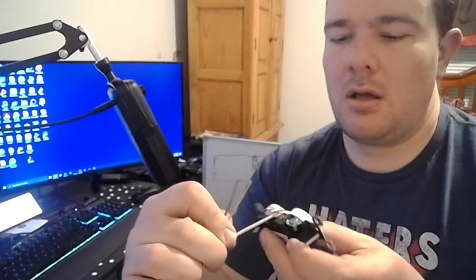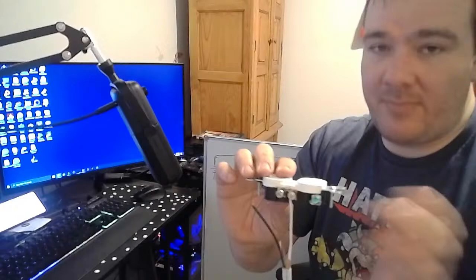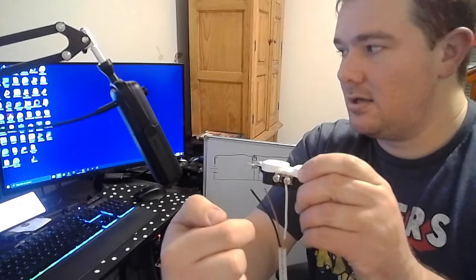All right. And the way that it folds over the screw is very important, at least to me. I was taught, and it makes sense, that you're going to be turning it to the right to tighten it. So you make the hook go over the same way that the screw is going to turn. So whenever you turn it and tighten it down, it's actually pulling the wire more in instead of pushing the wire out. We'll tighten this guy up.